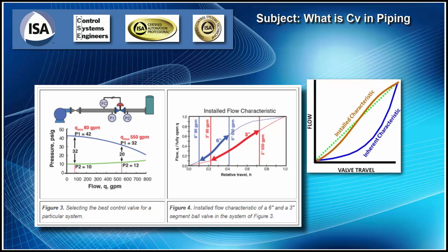And as we know, our pressure is dropping in the pipe on high flows and it's increasing on low flows. So as we slow down and close the valve down, we get a greater differential pressure. Even though we're closing the valve down, it's still trying to speed up the water because the pressure is increasing, and that's giving us more CV. But as we try to increase the flow and the valve opens up and the water starts flowing, the pressure drops. And so the CV also drops with that pressure.